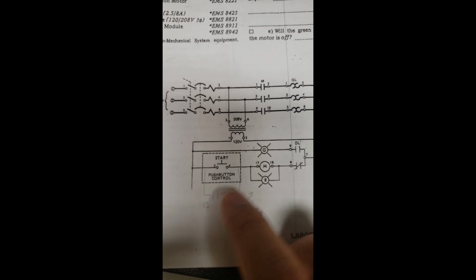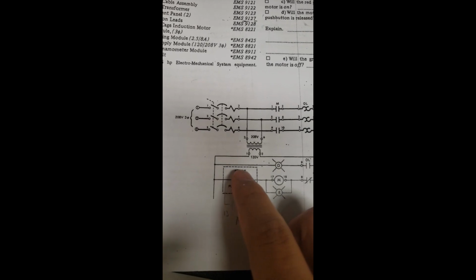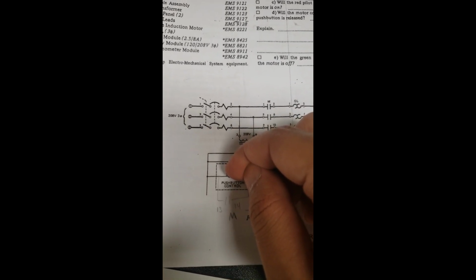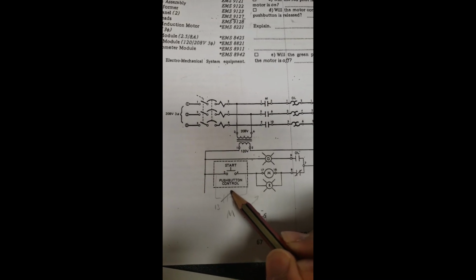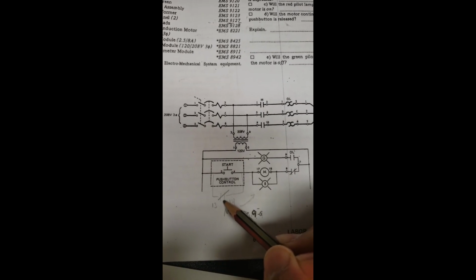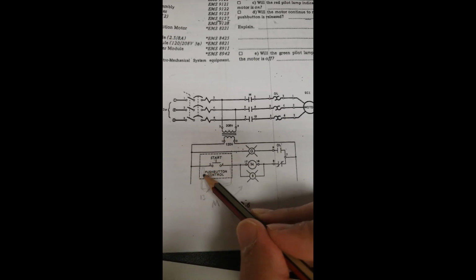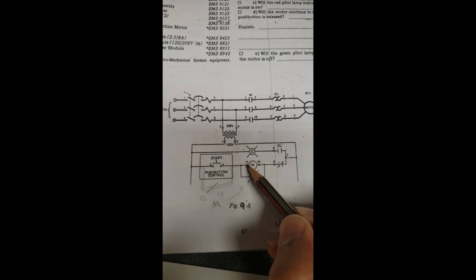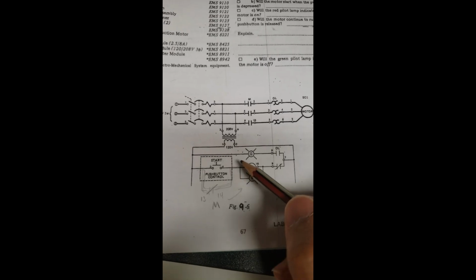To solve this issue, I have to put 13, 14, the normally open contact of the contactor. This one is the M contact, in parallel with the start push button. So if I press the start push button, this one will be energized, and this one will be turned to normally closed. If I release my finger, this one is still normally closed because the current will pass through the contact and still energize the contactor, and it will not stop. So even if I release my finger, the current will still pass through this branch to feed the contactor, and the motor will continue running even if I release my finger from the start push button.